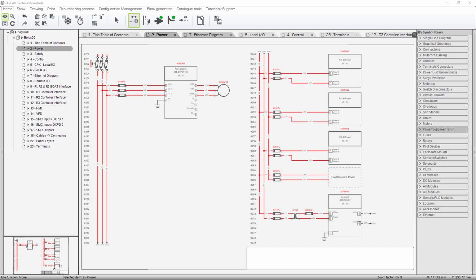Now remember that the fuses are there to interrupt the circuit to protect the wiring, not the load. So the fuses in that main disconnect are there to interrupt the current if the wires going from that disconnect to all of the fuse blocks exceed the rating. Now, coming off of the three-phase going to the variable frequency drive, I have another three fuses. Those are there to protect the wire going to the drive and to the motor. In my case, that drive is in the panel. So I'm not really protecting those wires as much as the wires going from the drive to the motor.